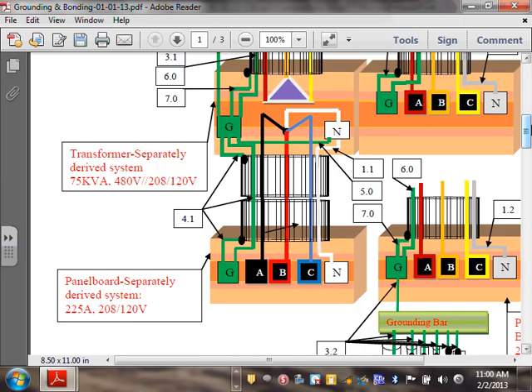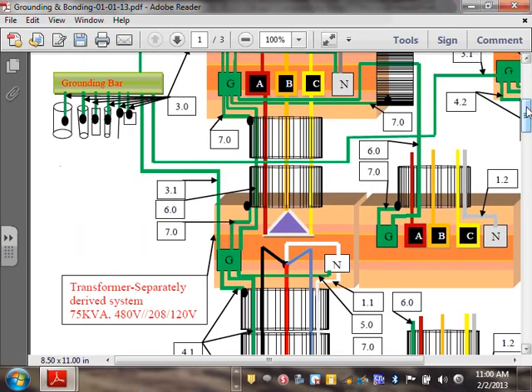So that's basically my bonding and grounding at the sub panel. Any comments about the bonding and grounding at the sub panel? Equipment grounding conductor, I bond the conduit, if it's metallic, from both ends with the proper fittings. Definitely, when you guys bond, they tell you if you have knockouts, that's a big deal. If the conduit matches the hole, then that's one bonding and grounding. If the conduit does not match the hole, meaning you have knockouts, you have half an inch, and you just got rid of the half an inch and you butcher half an inch.